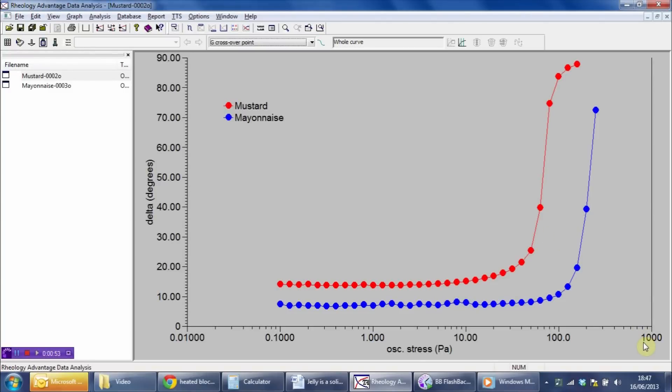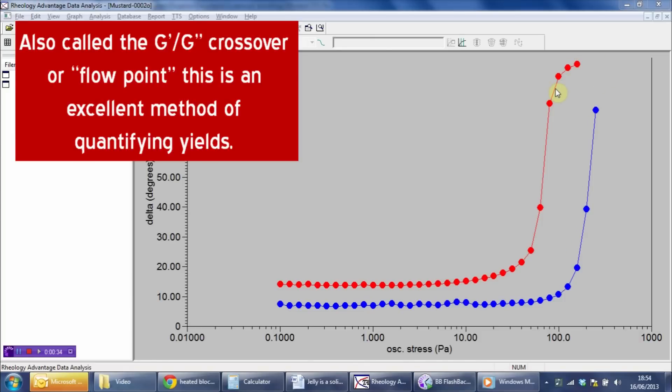However, undeniably, a single value for yield stress would be very useful for us from the point of view of comparing products. So, one method that we can use for getting a simple, single number yield stress value is to interpolate the stress at which the line crosses the 45 degree phase angle threshold. That is effectively the point at which the sample makes the transition from being what we call elastic dominant, i.e. more solid than liquid, to being viscous dominant, more liquid than solid.